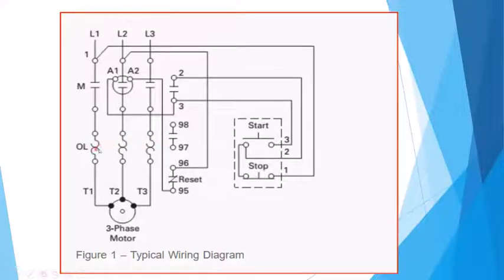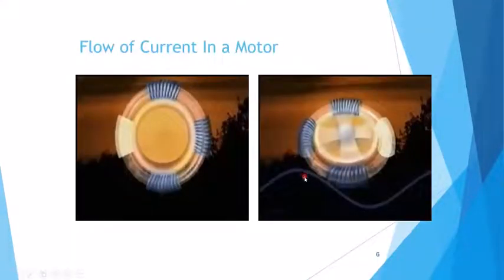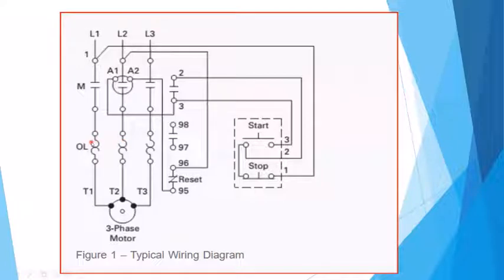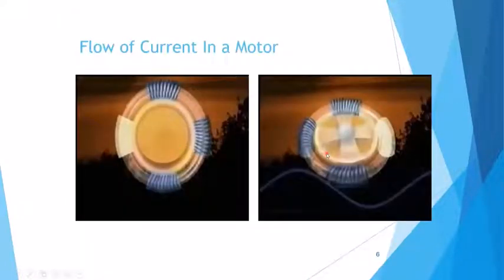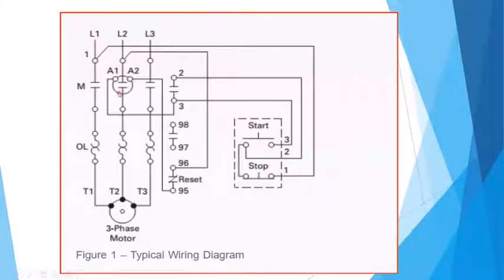What that does is if you're putting too much current to the motor, it'll actually cause failure. So they have these sensors in here, and then it simply opens up a set of contacts here that are in the start circuit. But originally we just basically turned it on. Well, when you turn it on this way, because the motor is not already creating what they call counter EMF, or voltage back, the motor will draw, depending on its resistance and inductance, between 3 to 6 times its nameplate. So if it's a 100 amp nameplate, it'll draw 300 to 600 amps very briefly just to start it up. And that's what the power companies want to get away from, so that they soft start.